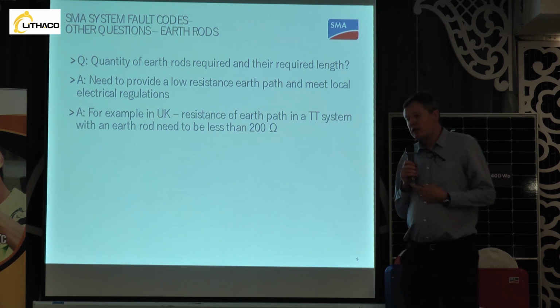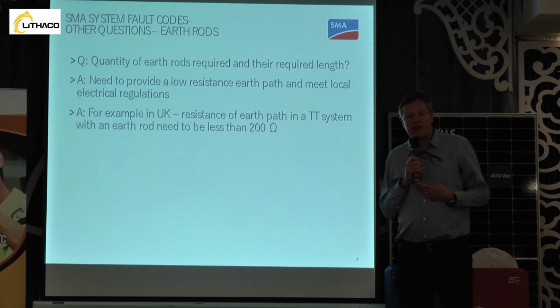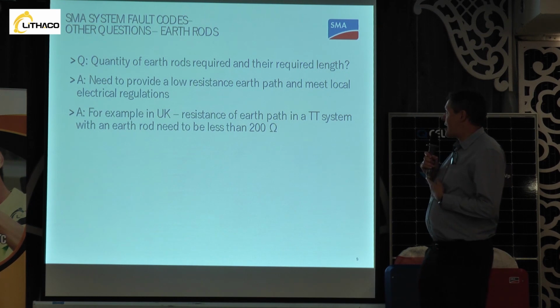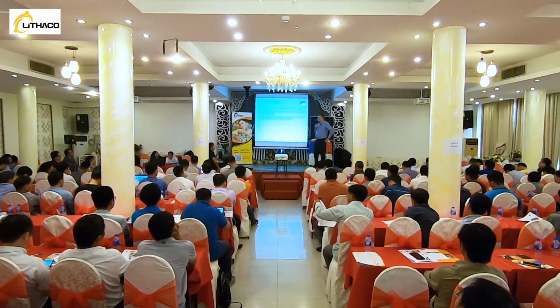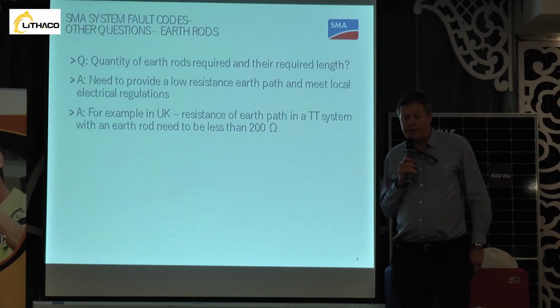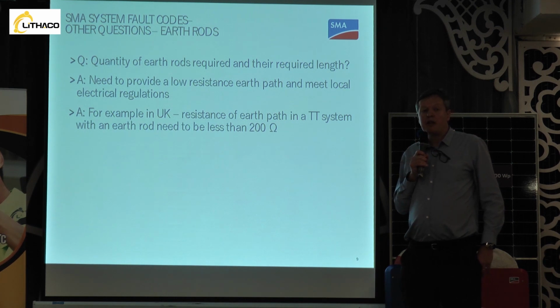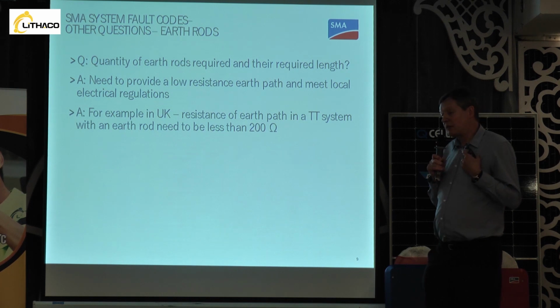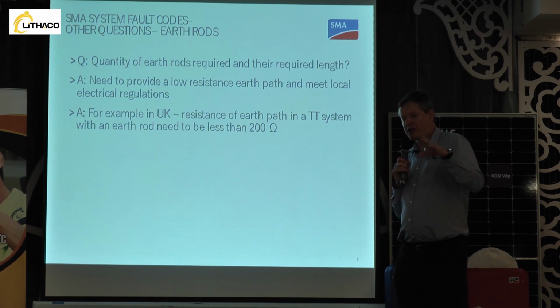So we have a question also about earth rods and earthing. You need to have a proper earth path, and you also need to meet the local regulations. What we would say here is, install the earth rod and then test it and make sure it provides the right earth path. I'm certainly familiar with the UK regulations, so you need a resistance of less than 200 ohms for the earth path, and I don't know what you need for your country, but it might be similar. We had the earlier fault code which was PE missing. You can switch that check off with the grid guard code, but we wouldn't recommend that.